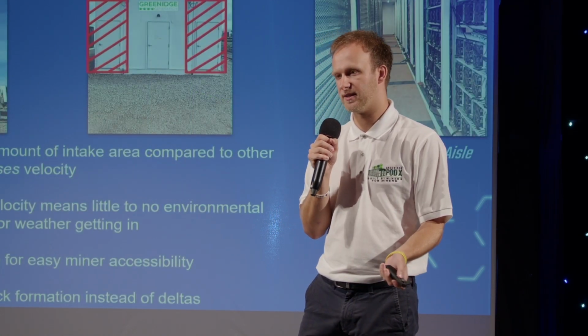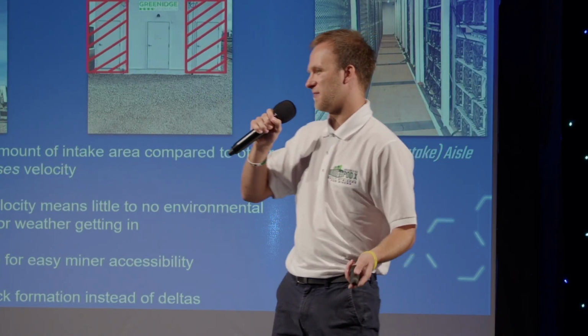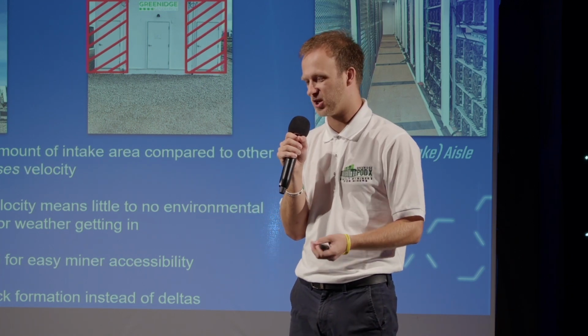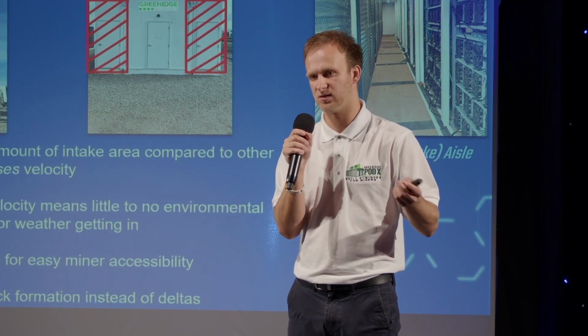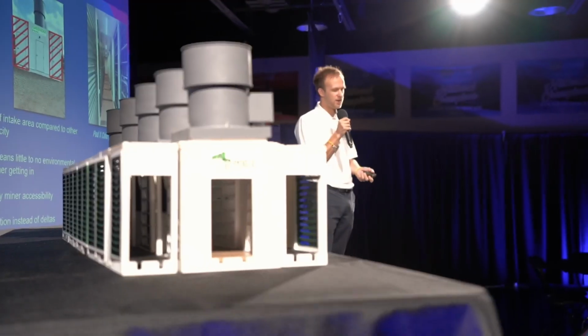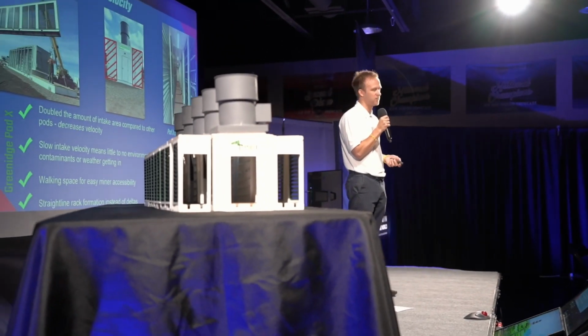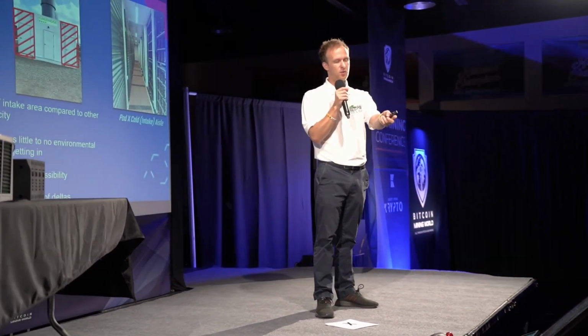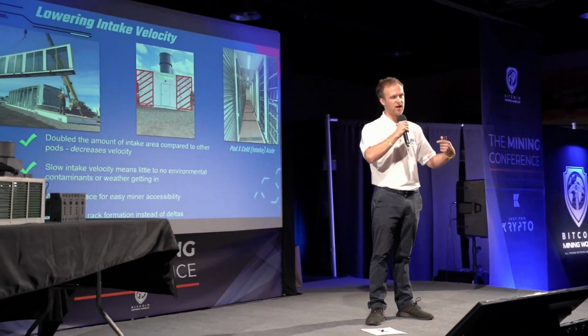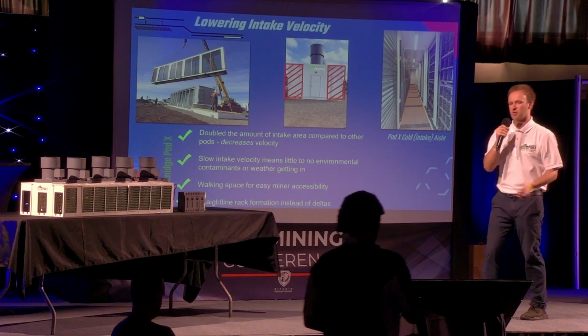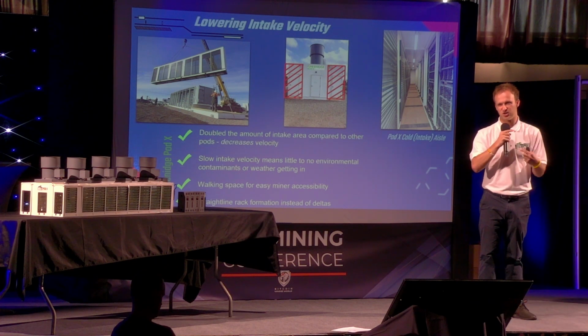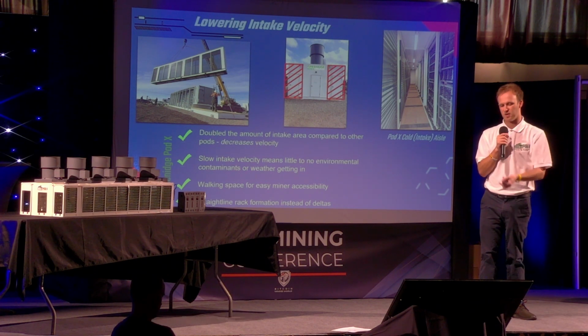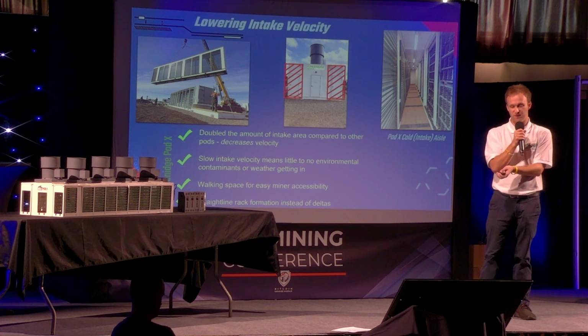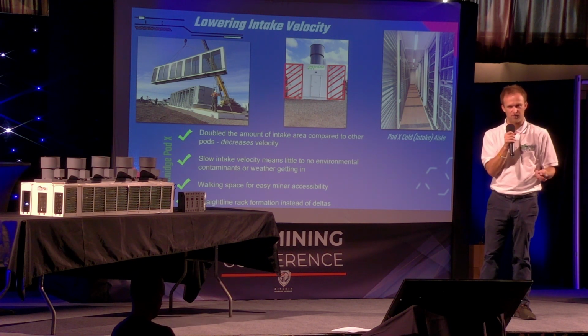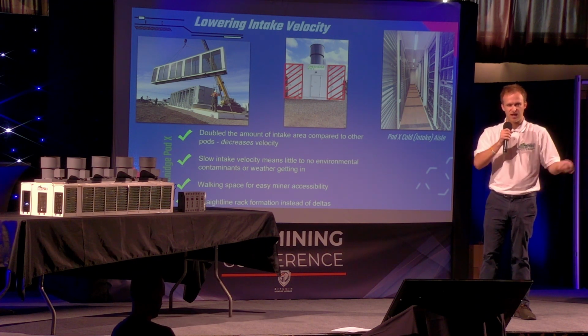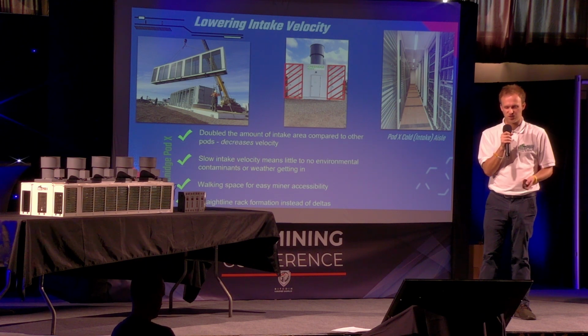And then we lowered our intake velocity. We did that by fixing the problem I told you about before. We increased our intake space by double the size, and that really helps to slow that intake air coming in. The way that our pod works is we have 2 intakes on both sides. You can enter both of them. This is a picture of the inside of one, actually. So we're sucking air in and then blowing it out through a hot aisle in the middle. And that intake space is about 4 feet. It's enough to slow the air down coming to the miner so it gets exactly what it needs, and we can run our miners much better and much more efficiently.